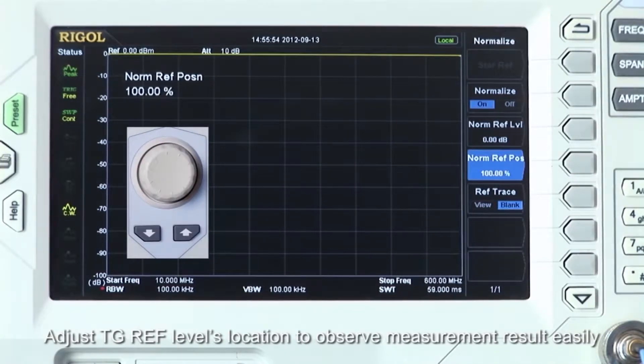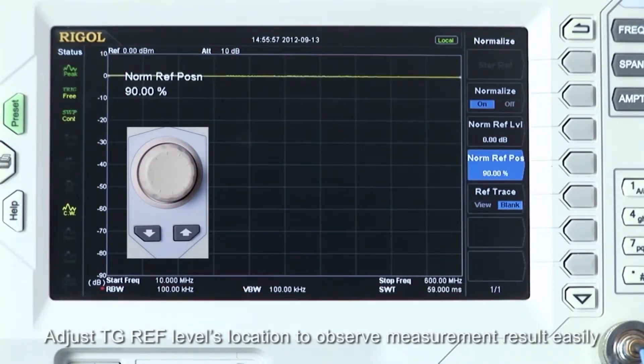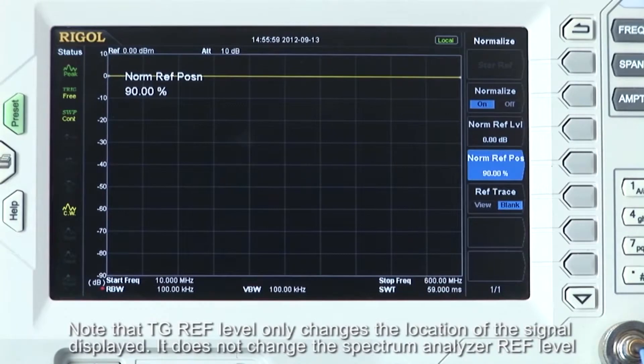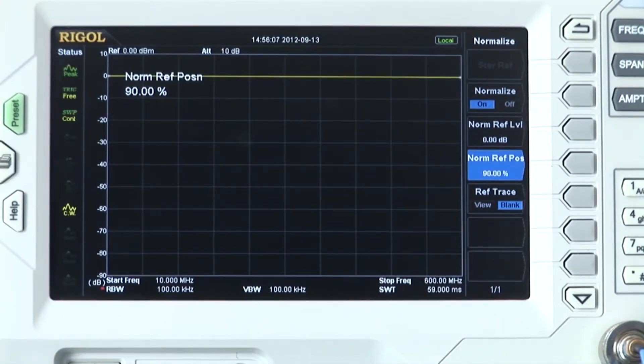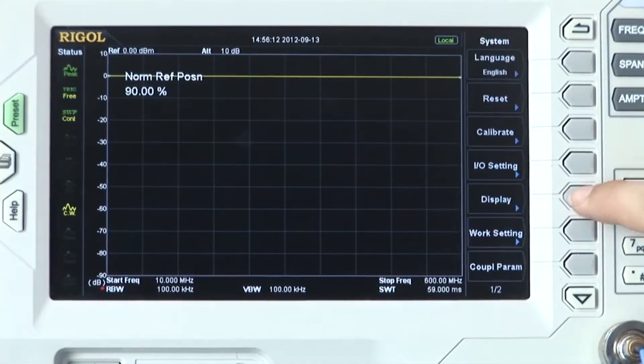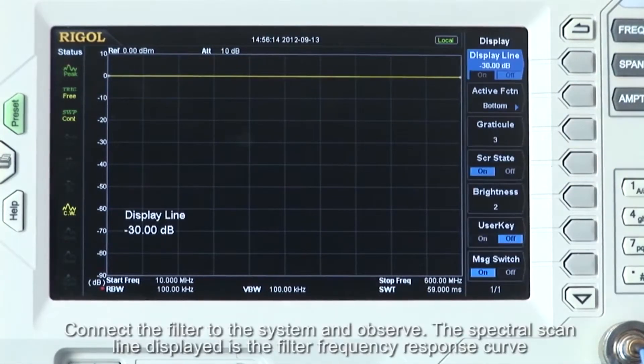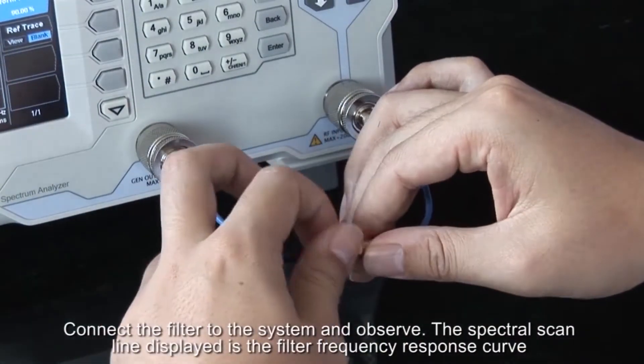Adjust the tracking generator reference level location to observe the measurement and results easily. Note: the tracking generator reference level only changes the location of the signal displayed — it does not change the spectrum analyzer reference level. To observe easily, we can set the active function area to a suitable location. Connect the filter to the system and observe. The spectral scan line displayed is the filter frequency response curve.